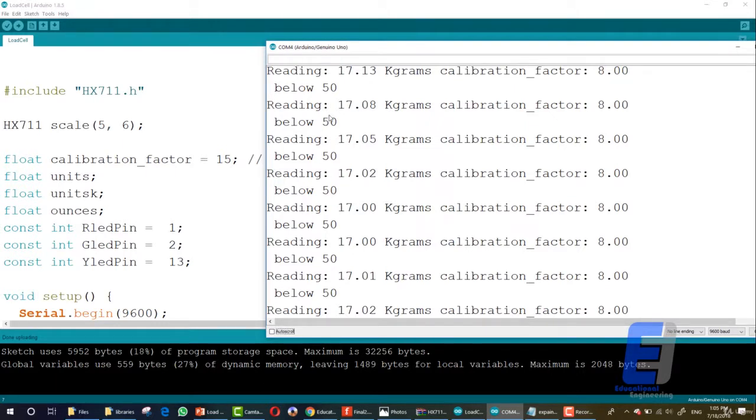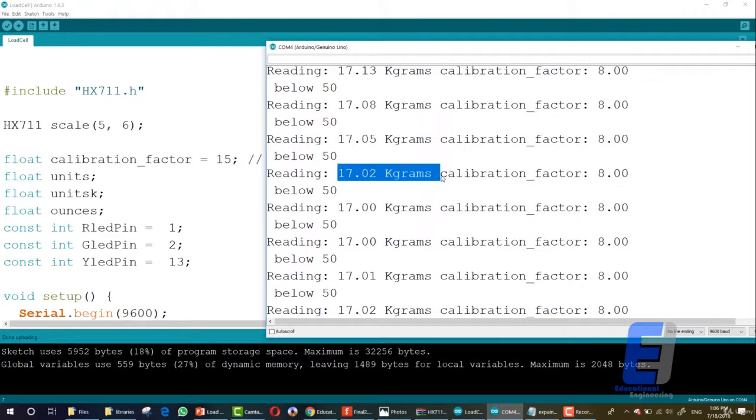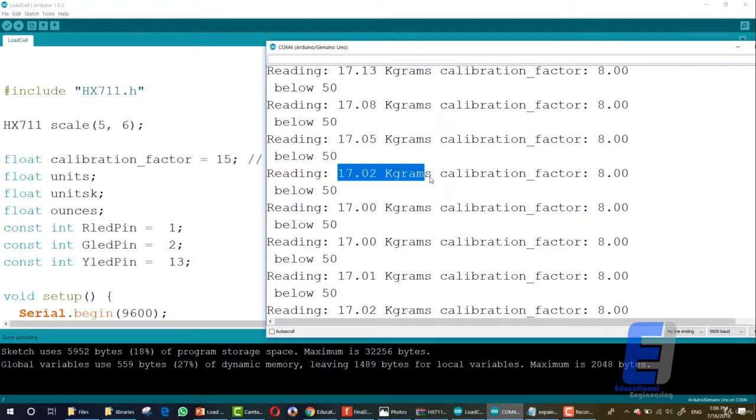You will keep increasing or decreasing the calibration factor using the plus and minus signs. Once you get the calibration factor right, you will see the kilograms. If you are placing one kilogram, you will see here one kilogram. You will know that this is the right calibration factor.